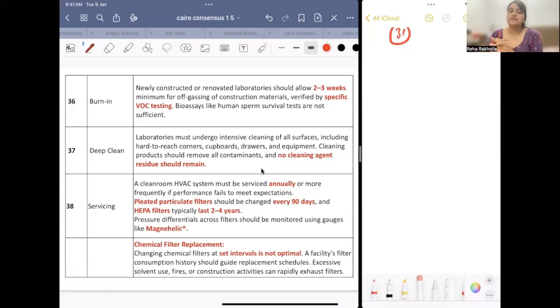Then deep clean. You see, the laboratory should get intensive cleaning of all surfaces, including hard to reach corners, cupboards, drawers, and equipment. Cleaning products should remove all contaminants, but we would not allow any cleaning agent residue also. We'll again clean it with distilled water or sterile water. Then servicing. A clean room HVAC system must be serviced annually, or more frequently if performance fails to meet expectation.